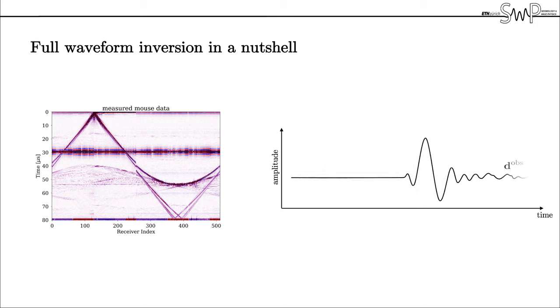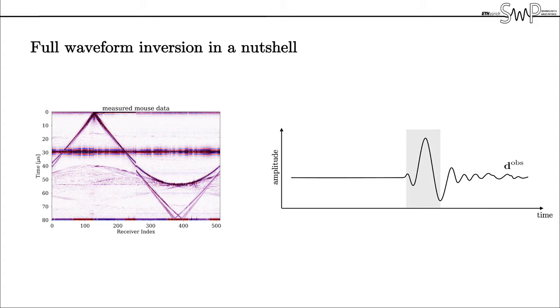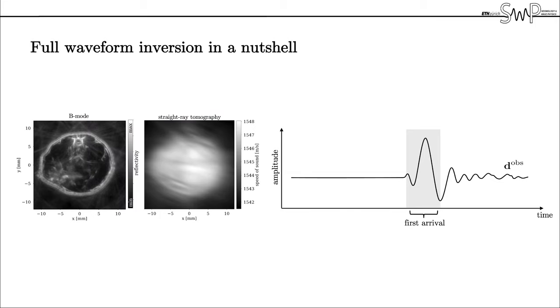To extract an image the signal information is most commonly limited to the first arriving pulses from which the time of flight or travel time of the wave from the emitting element to the receiving elements is calculated. With this kind of information we can reconstruct reflection or B-mode images as seen here on the left that qualitatively image the internal structure of the object or we can generate quantitative reconstructions of the speed of sound values with linearized methods as for instance straight ray tomography seen here on the right.